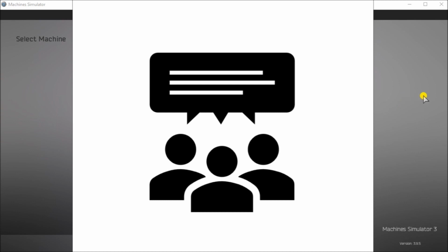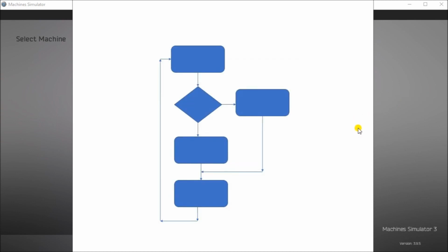Next, once we have that, we should develop a logical sequence of operation. This is where the majority of your time is going to be spent in PLC program development. Steps 1 and 2 allow you to systematically express what has to happen in the PLC program. So you grab that information and then you start laying it out. In this particular case, we can use a flowchart or we can use a sequence table, either one, as long as you fully understand at every step what has to happen within the logic.